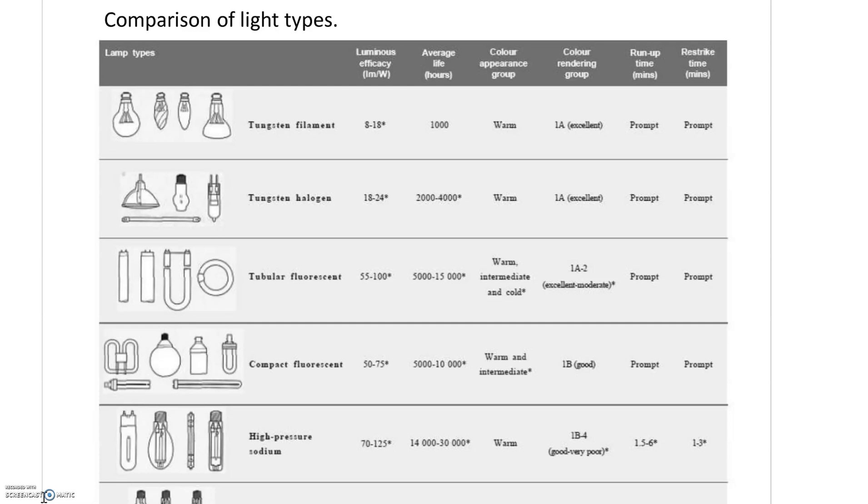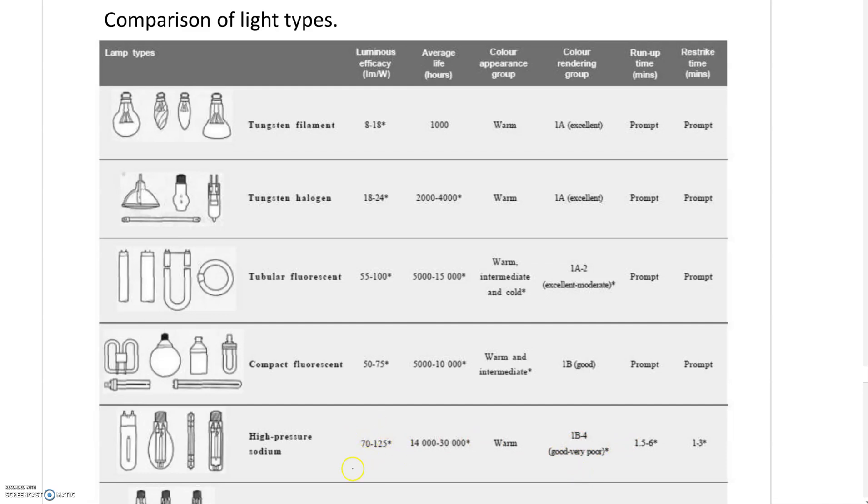In a car showroom you want colors to be vibrant, reds really red. At meat counters you want meat to look the right color, not green. An example of very poor color rendering is high pressure sodium, which produces orange street lights. However, their efficacy is very good with excellent lumens per watt and very good average lifespan.